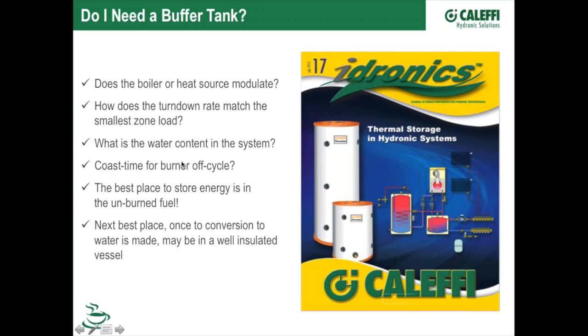So again, that can help you match your system to your heat emitters. If you've got a lot of small zones that were causing the burners to cycle on and off frequently, we're just going to add a little bit of volume, a little bit of capacity to the system. We made this stubby version. This guy said, gosh, it'd be nice if we had a tight mechanical space where we've got to get this and the boiler in the same space. Mount the boiler up above this, mount the tank below it, and now in a footprint probably less than 2.5 to 3 feet wide, you've got both your buffer tank and your boiler mounted in one spot.